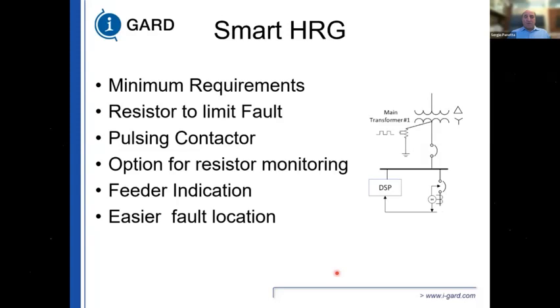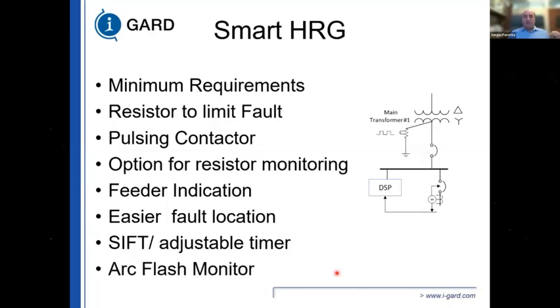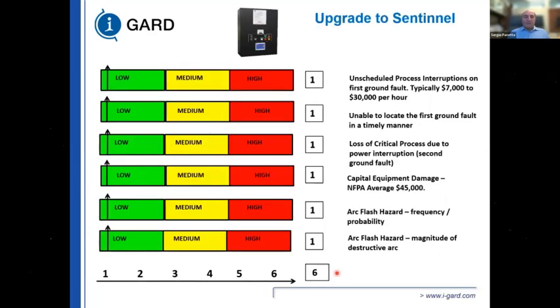Easier fault location. Now we have the ability to put in SIFT, selective instantaneous feeder trip. So we can monitor every single feeder to detect the presence of the fault and isolate the feeder that the second fault is on in a timely manner, and an arc flash monitor.